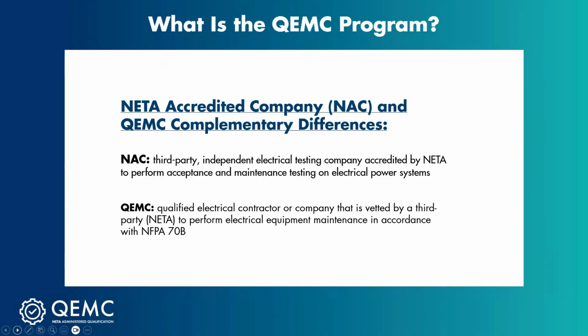So, the differences: NETA is the association behind both programs, and it may seem a little difficult to discern which is which. NETA has been a great powerhouse in the industry, providing independent electrical testing companies the certification and qualifications to provide third-party independent acceptance and maintenance testing on electrical power systems. QEMCs, by contrast, provide the maintenance services, but not necessarily the acceptance testing criteria. The QEMC is more vetted by NETA to perform the electrical equipment maintenance in accordance with 70B.